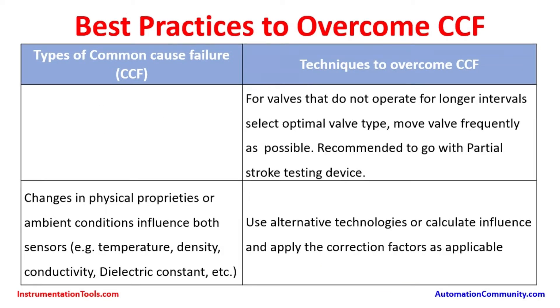For valves that do not operate for longer intervals, select the optimal valve type and move the valve as frequently as possible — meaning opening and closing. It is recommended to go with a partial stroke testing device, which is another technology for safety instrument system valves. The partial stroke testing device moves the valve to a certain extent.